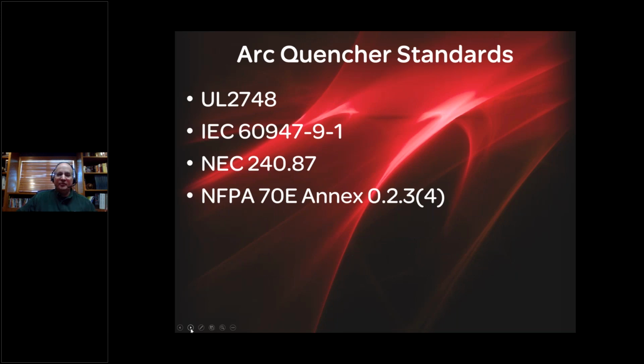In terms of the standards, arc quencher devices are defined and listed by UL under UL 2748. I believe at present we have the only resettable solution that's UL 2748 listed. The equivalent international standard is 60947-9-1.